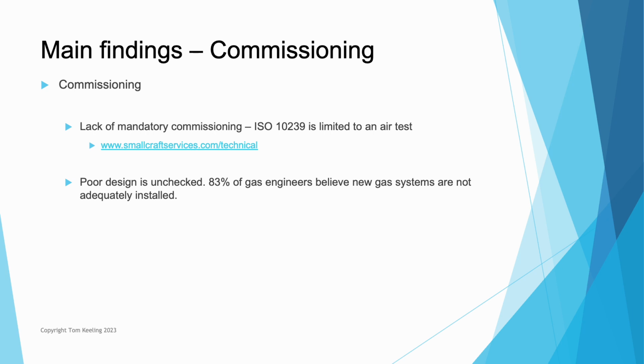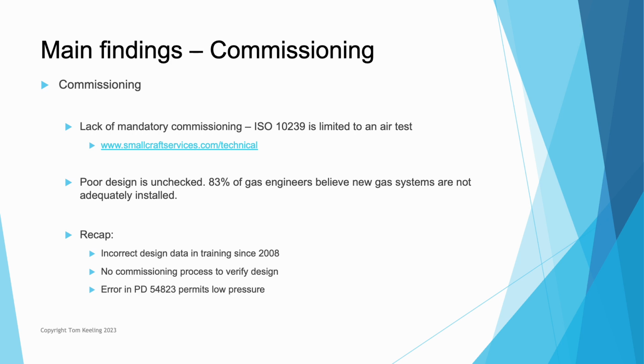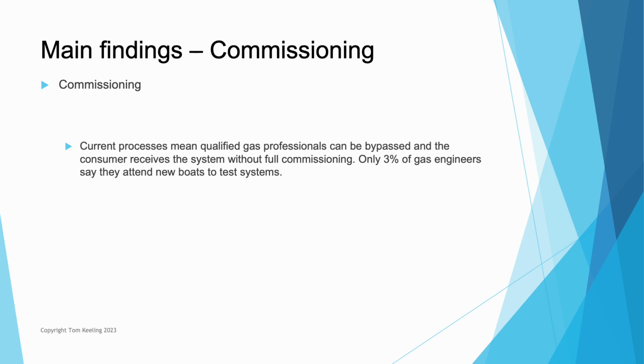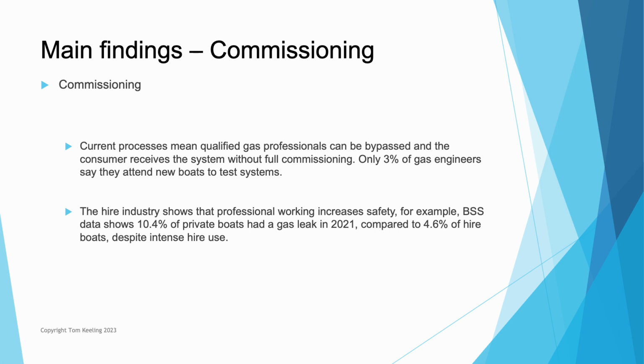So essentially this poor design that we found is being unchecked, and 83% of gas engineers when interviewed believe that new gas systems are just not adequately installed. So to recap then, that's incorrect design data in the training since 2008. There's no commissioning process to verify the design, and the error in the PD is permitting the low pressure to exist. Current commissioning processes mean that qualified gas professionals can be bypassed and the consumer receives the system without full commissioning. Only 3% of gas engineers say they attend new boats to test systems.